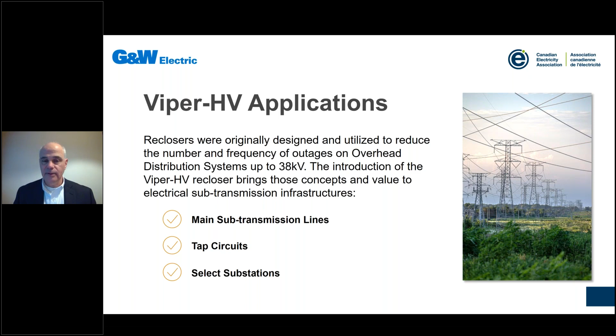The application of reclosing is a concept we can all understand, and it exists in substations today. It's the ability, through current detection, to find an adverse current or voltage condition and turn off the circuit. Quickly isolating that adverse condition—if it's temporary—allows a very short outage and complete restoration once the fault clears.